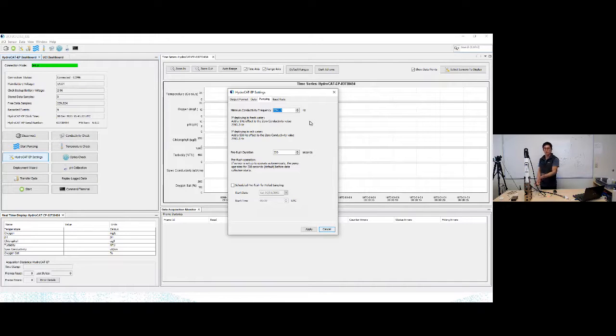So even if your instrument is logging, if your conductivity sensor is not outputting a value that is higher than this setting, your pump is not going to turn on. It's a fail-safe to prevent your pump from running after you pull it out of the water, but forget to tell it to stop sampling, so that you don't damage your hardware.